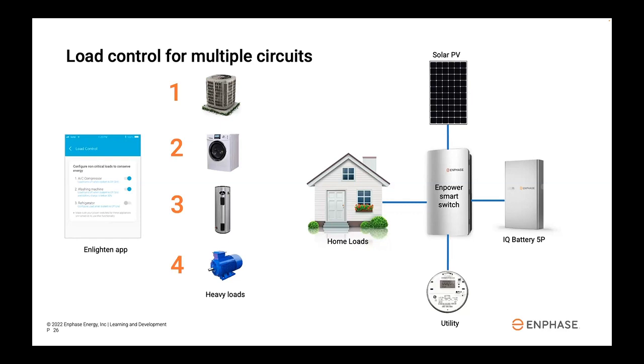There are multiple operating modes to choose from with load control. You can set it to basic mode, where the load is simply shed if the system goes into backup operation. You can also set it to shed loads based on a schedule. And lastly, you can program it so the load has power if an integrated generator is running, but if that generator turns off, the load would be shed. Load control is another feature that improves the overall resilience of the system.